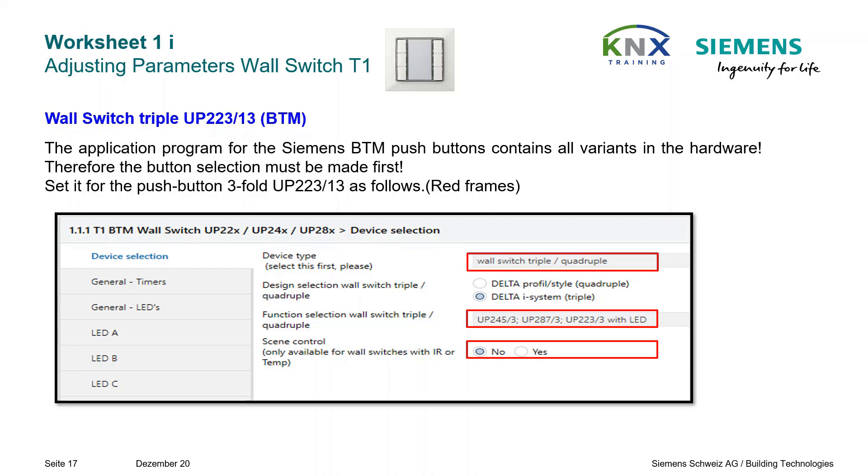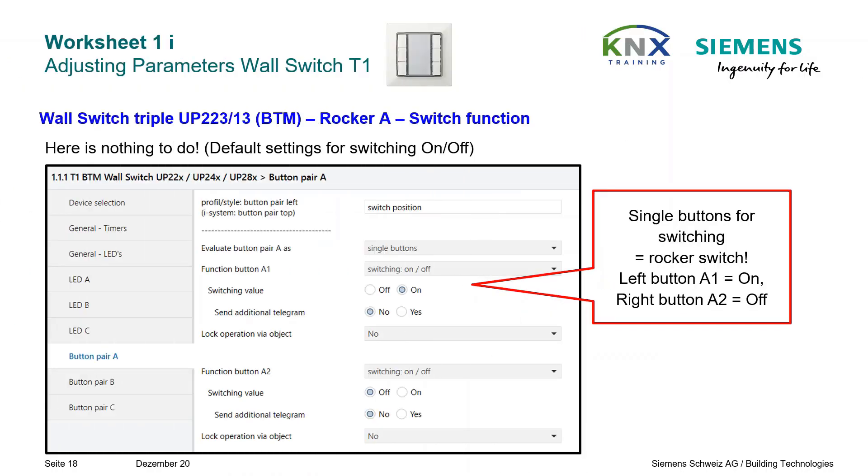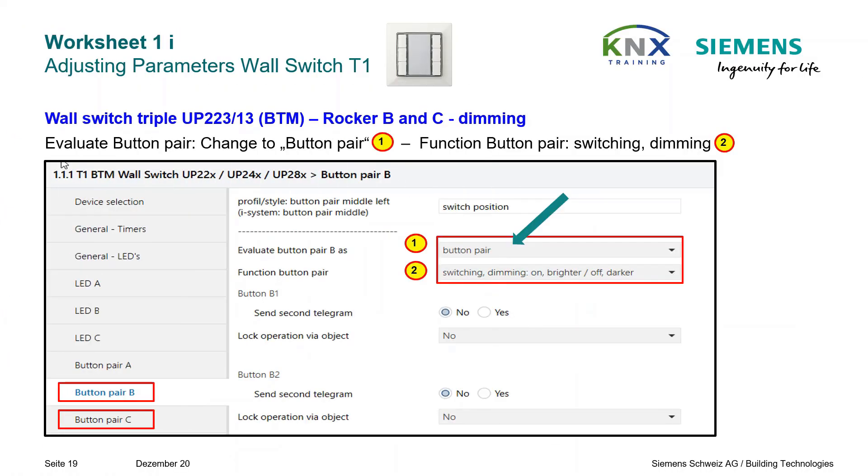Set this for the triple UP223/13 pushbutton as shown — see red frames. Now the rockers are parameterized from top to bottom. The top rocker switches conference ceiling light, and the default setting is already correct. For rockers B and C, the rocker evaluation must be set as a button pair. This will also change the function selection so that it now includes dimming, which is desired. So nothing else has to be changed.